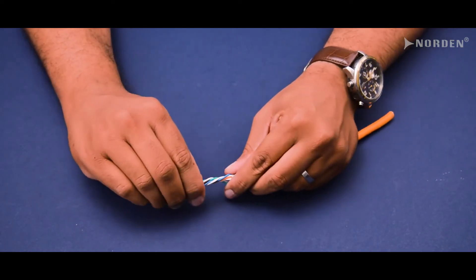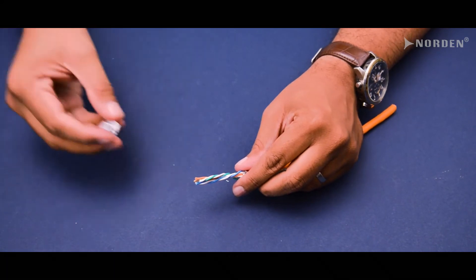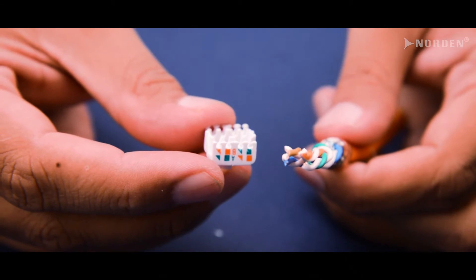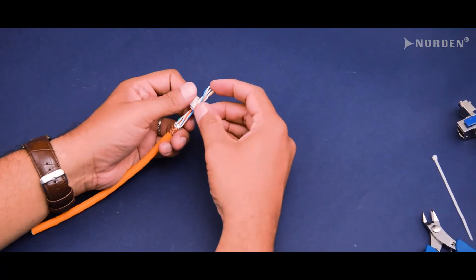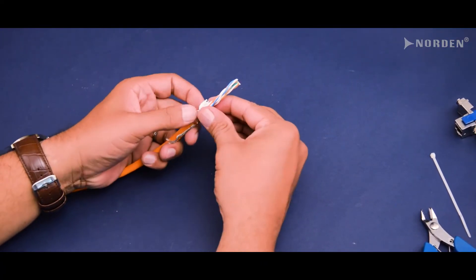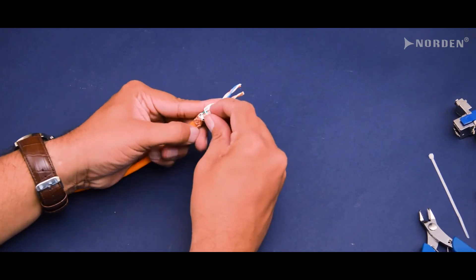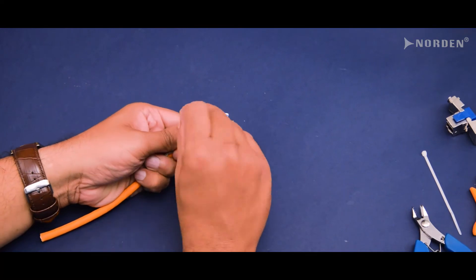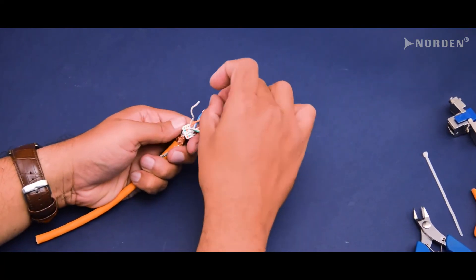Next, take the keystone jack termination cap. The cap has a printed color code for 568A and 568B wiring on both sides. Place the cable inside the termination cap and insert each pair as per your desired color code. Please make sure all conductors are fully seated in the slots and in the correct position.